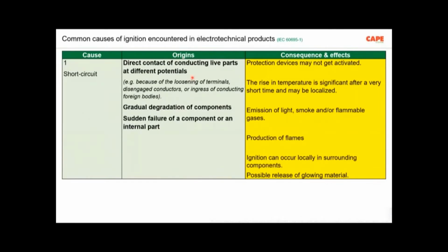In case of a fire, a person who knows the standard can actually do the investigation in a better way. But as I said, it is not one standard, even though I put it as one. There are several substandards, I think about 30 plus standards. So the first cause of electrical fire is short circuit. Why does it happen? It is happening because of a direct contact of conducting live parts at different potentials.